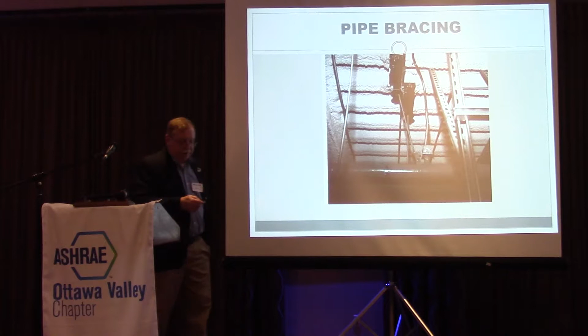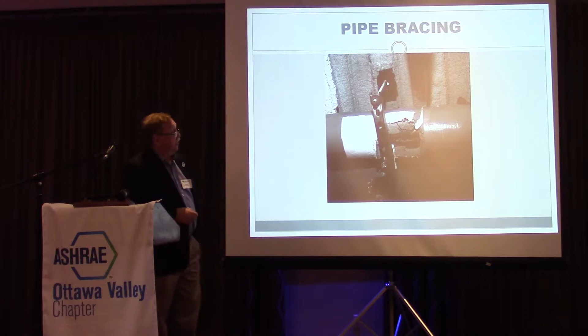This one here was a small trapeze they had made. As you can see, there was an insulation guard here, and it fell out somewhere, probably right at the very beginning after a couple of moves back and forth. But what I want to show you is this - see all this scratching? That's the pipe sliding back and forth on that trapeze. They could see 100 cycles back and forth on that pipe, moving back on top of that trapeze. A lot of movement can be seen during an earthquake.